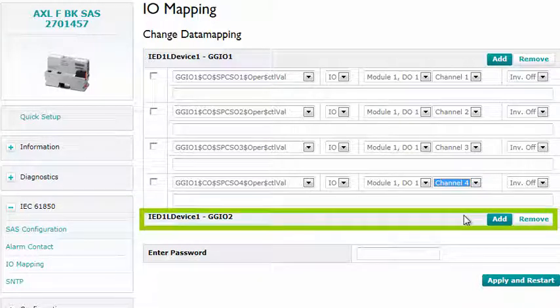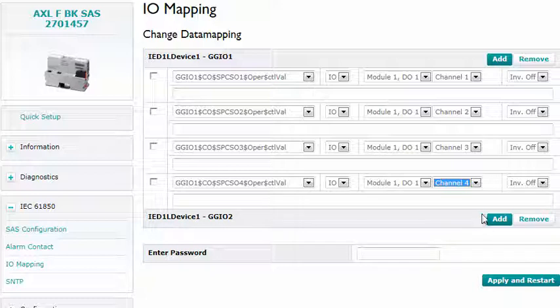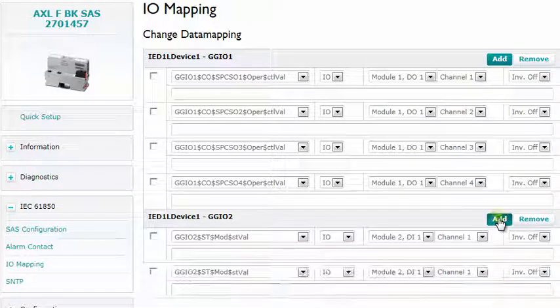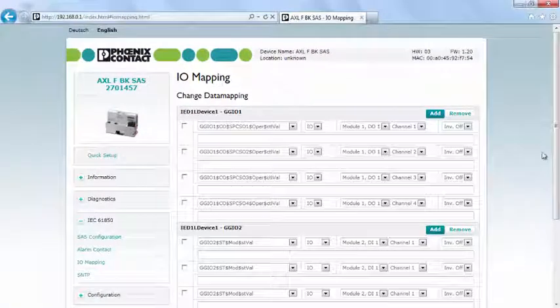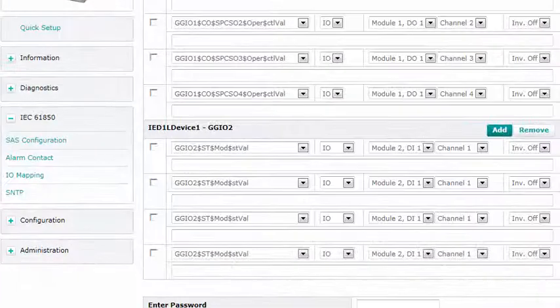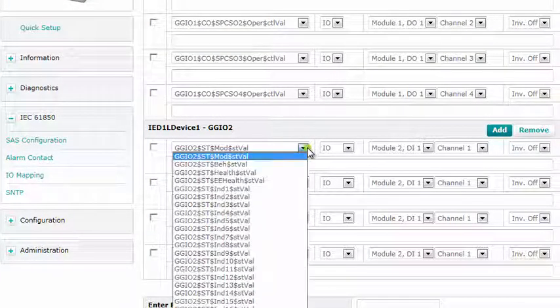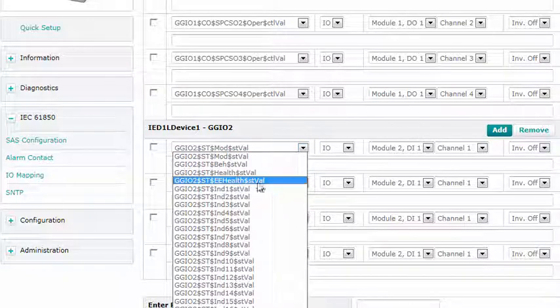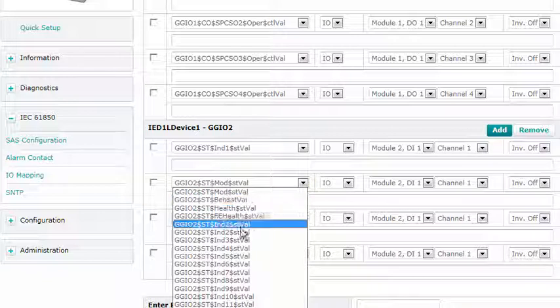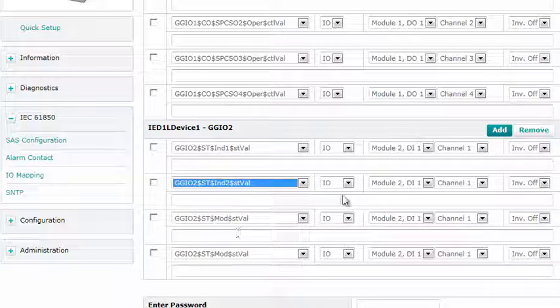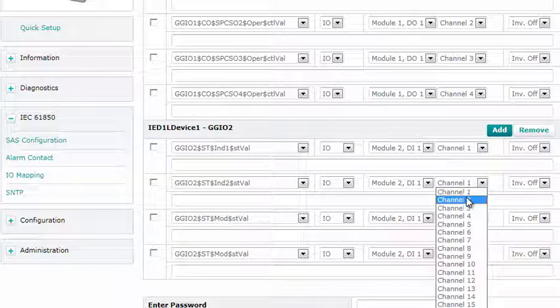The IEC 61850 attribute control value is selected and the output module and channel are assigned. GGIO2 describes the 16-channel input module. To assign the signals, press the add button each time. The IEC 61850 attribute status value is then selected and the input module and channel are assigned.